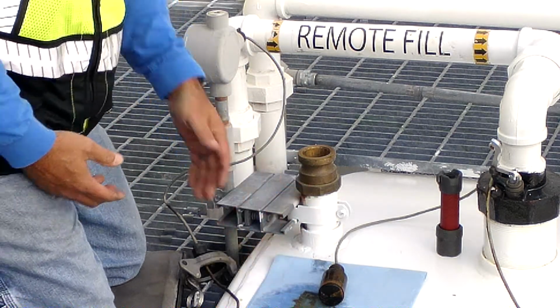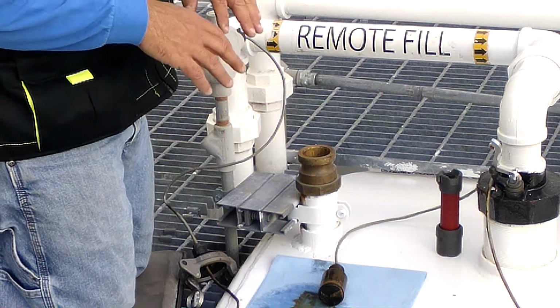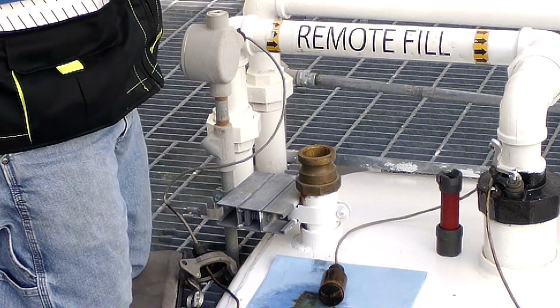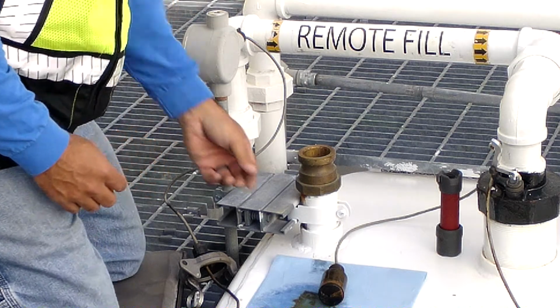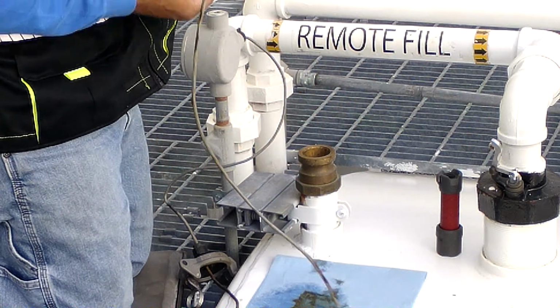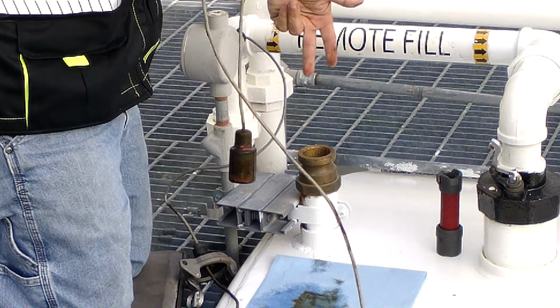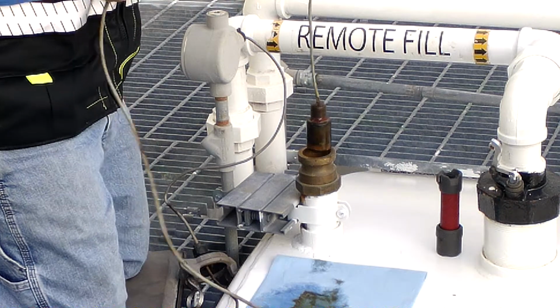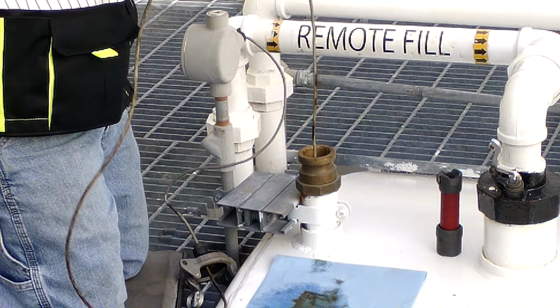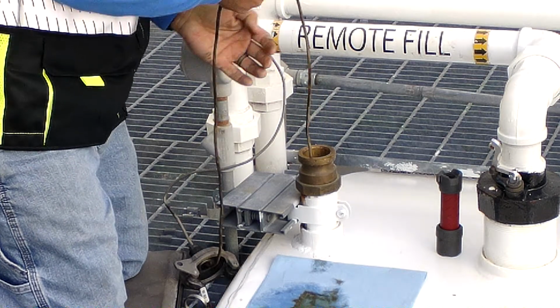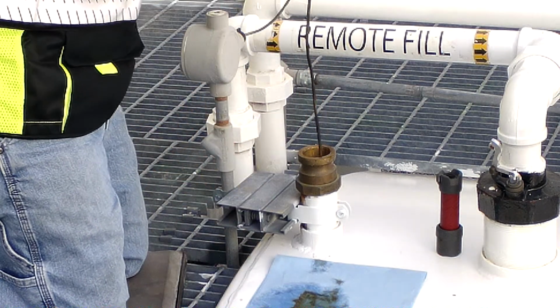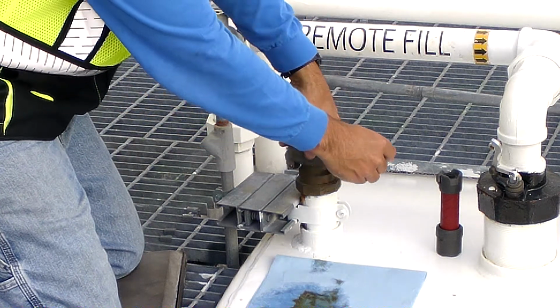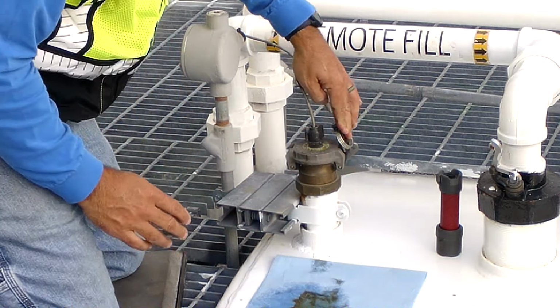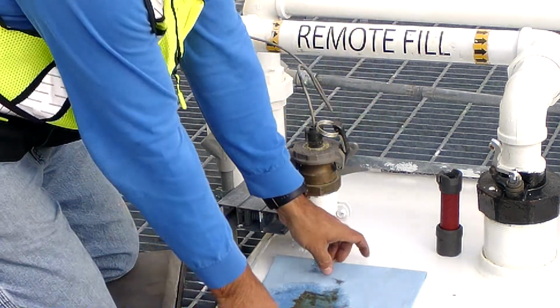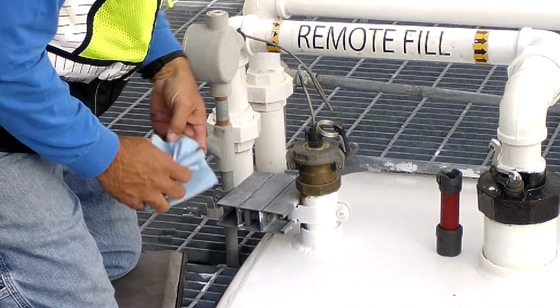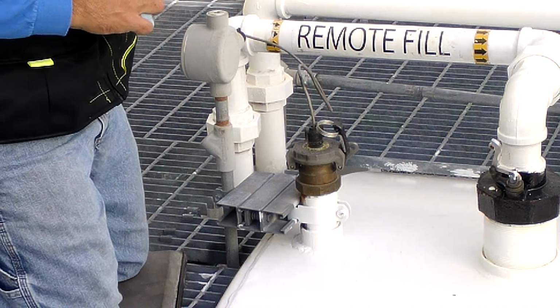Obviously, with the presence of water, it initiates the requirement for ultrasonic thickness testing on the lower third of the tank to verify inside-out corrosion of the secondary. So now that we've done the inspection, we verified that the sensor is functional. We've identified the presence of water and we've taken our pictures. We will go ahead and reinstall the sensor carefully. Resecure the cap, lock it in place. There's an option for a padlock here. Clean up our tools and move on to the next component of this tank.